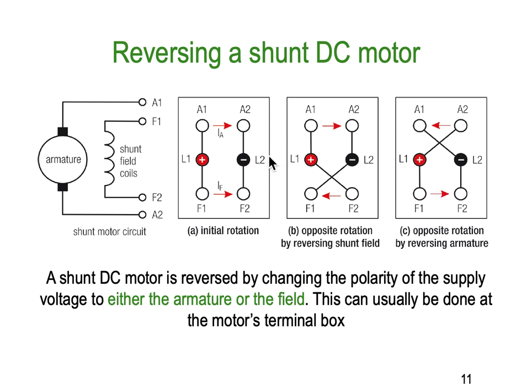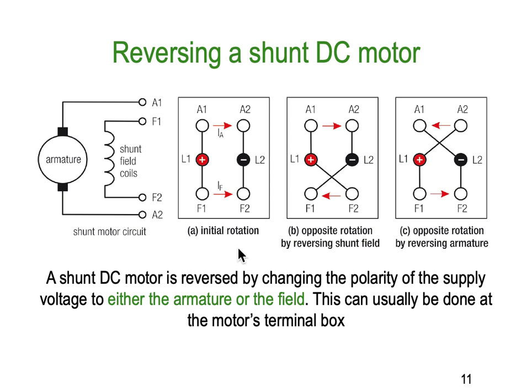Reversing a shunt DC motor is a little more tricky because quite often the shunt and the armature are being fed together at the same time. Normally we would have our armature and our field connected in parallel with our supply. We either have to reverse the field or we have to reverse the armature — but not both. A shunt DC motor is reversed by changing the polarity of the voltage to either the armature or the field, and this can be done at the motor's terminal box.